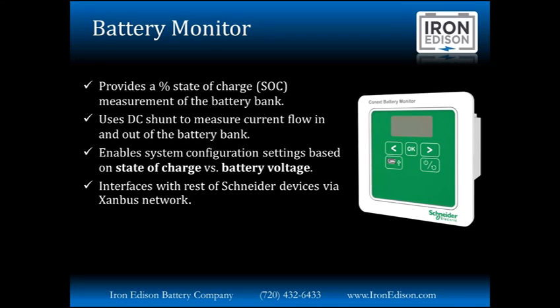And by having this, the battery monitor will report that state of charge through the Xanbus network to all the other devices, inverters, charge controllers, etc. And by having that information, you can use that more detailed state of charge number to trigger various events like recharging the battery, triggering a generator start, switching to and from the grid for backup, things like that. So it's a very handy add-on accessory for more detailed control and management of the system.